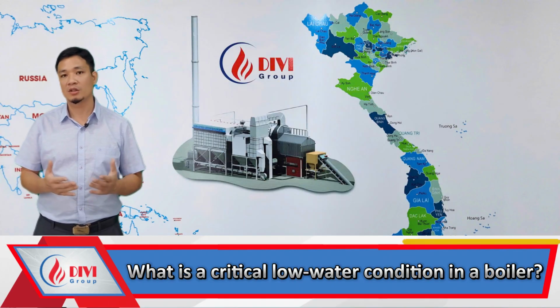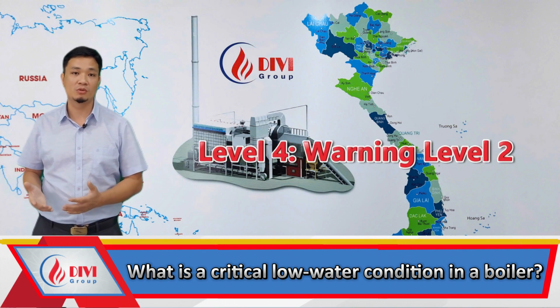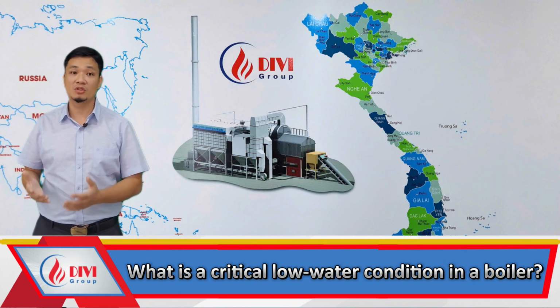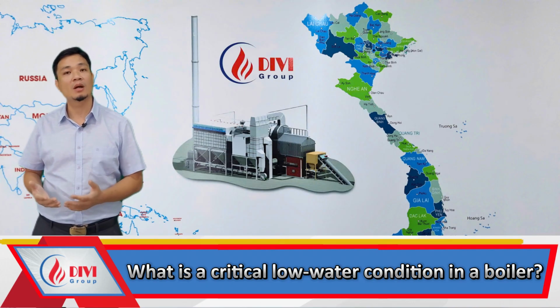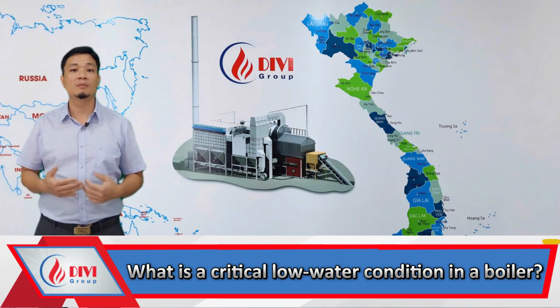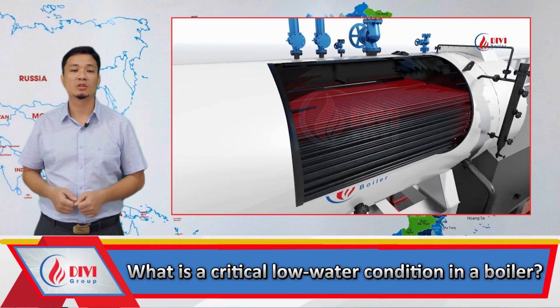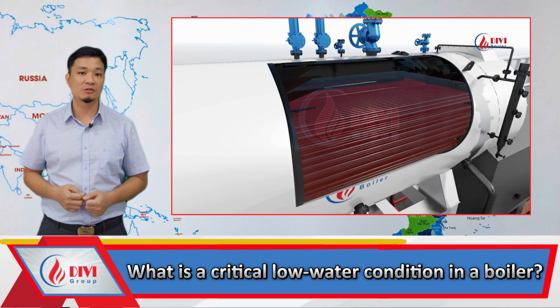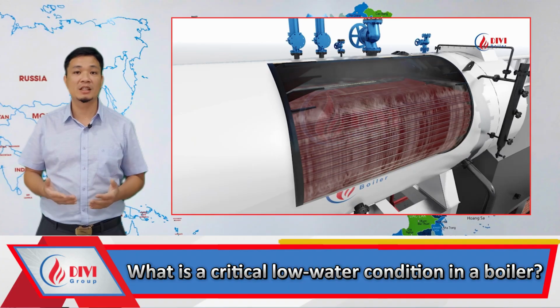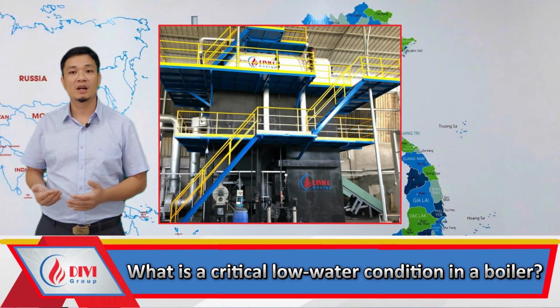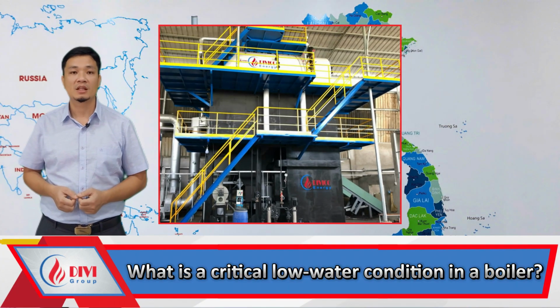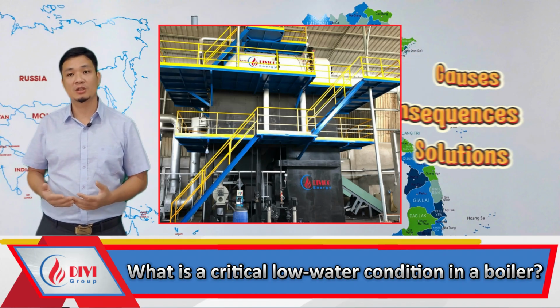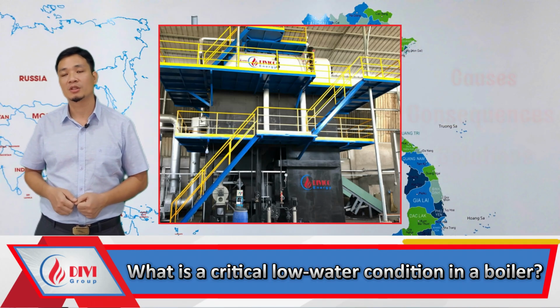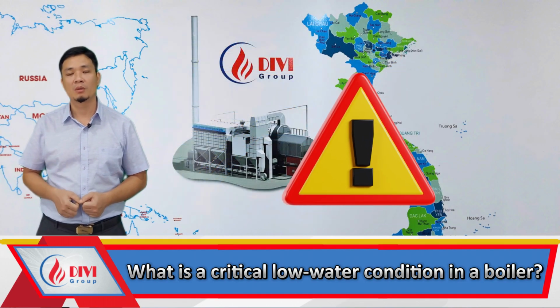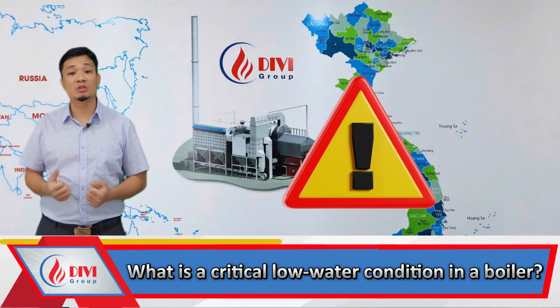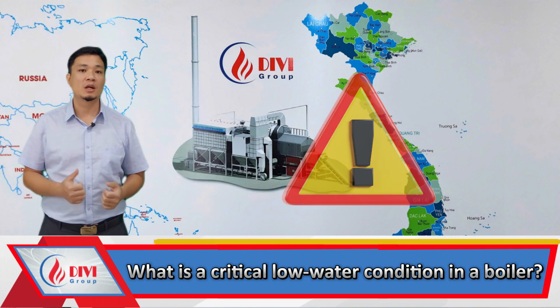A boiler dryout occurs when the water level falls below level 4, indicating an extreme loss of water. This is the most critical and hazardous situation in boiler operation. The heat transfer tubes are no longer submerged in water and continue to receive heat input, leading to overheating and possible rupture. If your factory relies on steam boilers, take a few minutes to fully understand the causes, consequences, and emergency procedures. Remember, a boiler operating without water doesn't just destroy equipment, it can endanger lives.